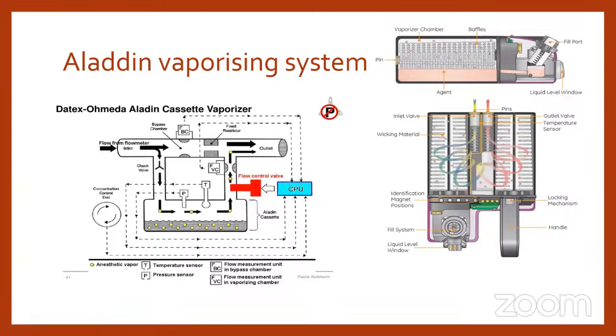So when we want to deliver some amount of anesthetic agent to the patient, we set that in the computer, and the computer will automatically maintain the temperature, the flow of the system, and the volume that flows. It automatically adjusts every setting and delivers the required amount of anesthetic agent to the patient. So this is the CPU that controls the flow control valve.